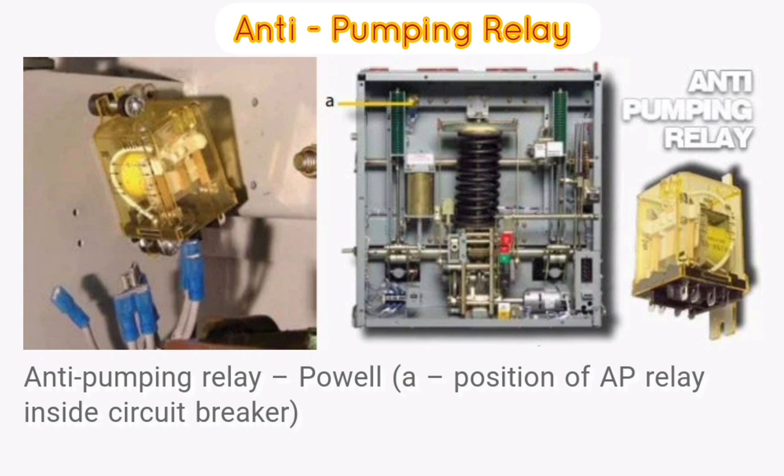The anti-pumping relay is basically a NO contact. This means when the circuit breaker is in the closed condition, the relay will be in NO condition, and when the circuit breaker is in the open state, the relay will be in NC condition.